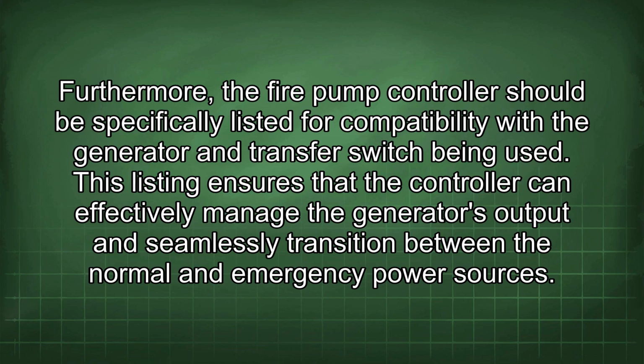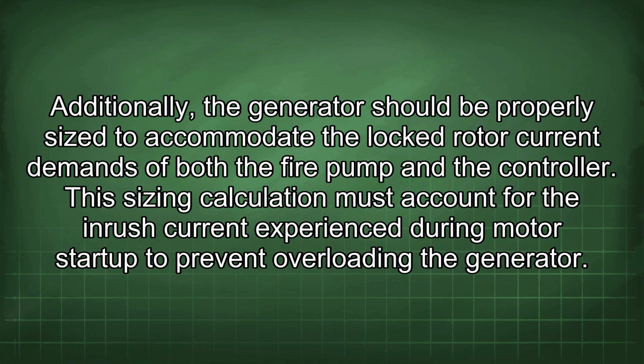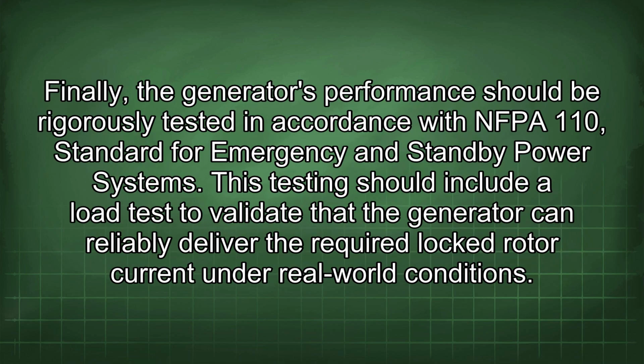power sources. Additionally, the generator should be properly sized to accommodate the locked rotor current demands of both the fire pump and the controller. This sizing calculation must account for the inrush current experienced during motor startup to prevent overloading the generator. Finally, the generator's performance should be rigorously tested in accordance with NFPA 110, standard for emergency and standby power systems. This testing should include a load test to validate that the generator can reliably deliver the required locked rotor current under real-world conditions.